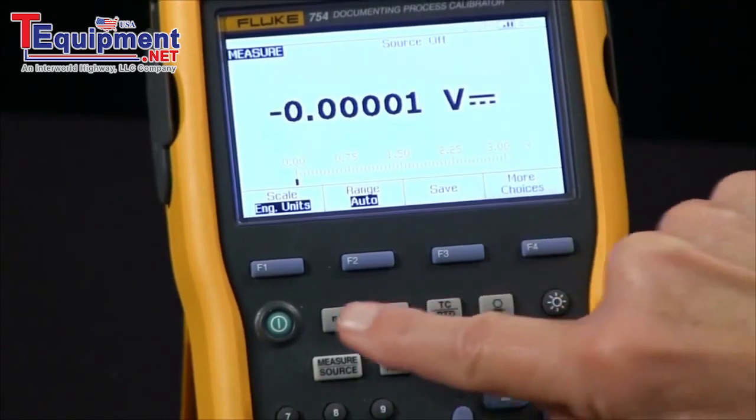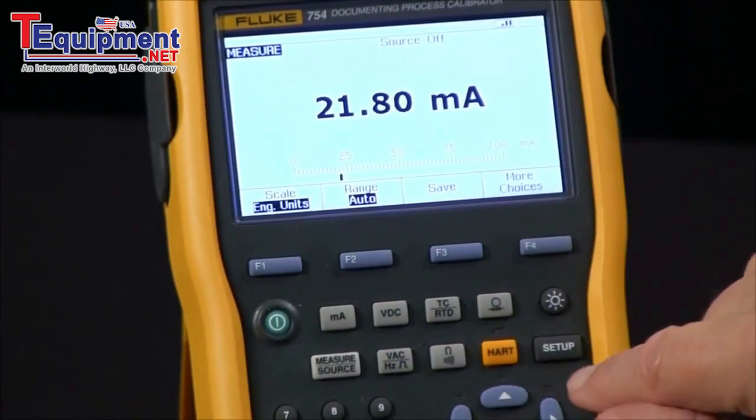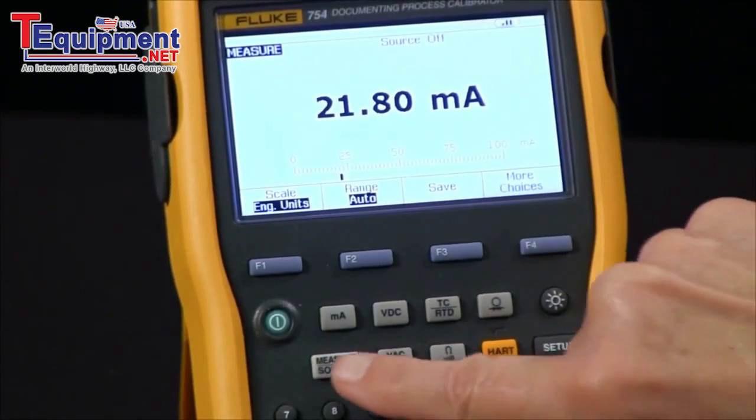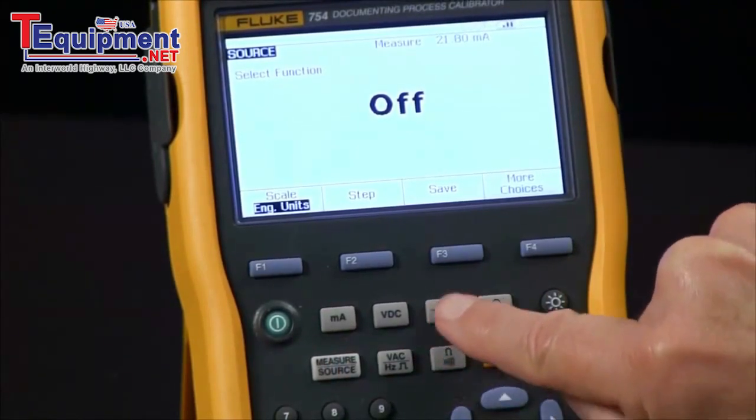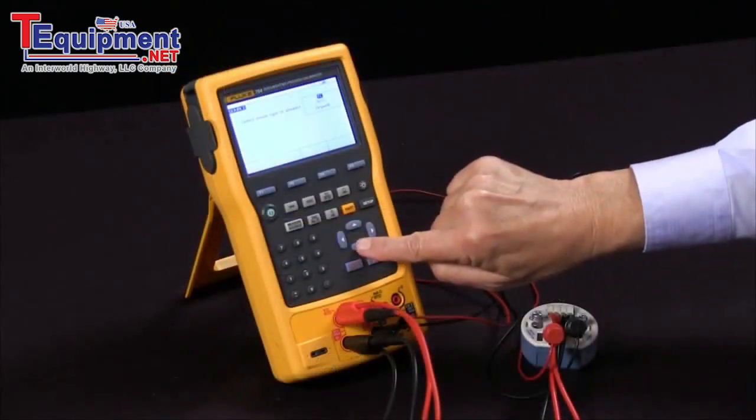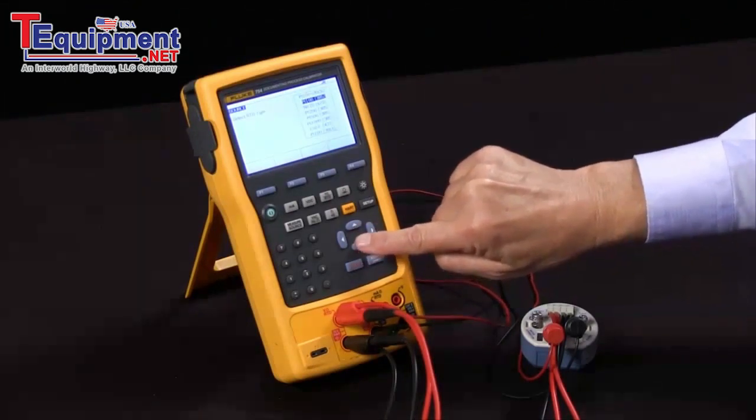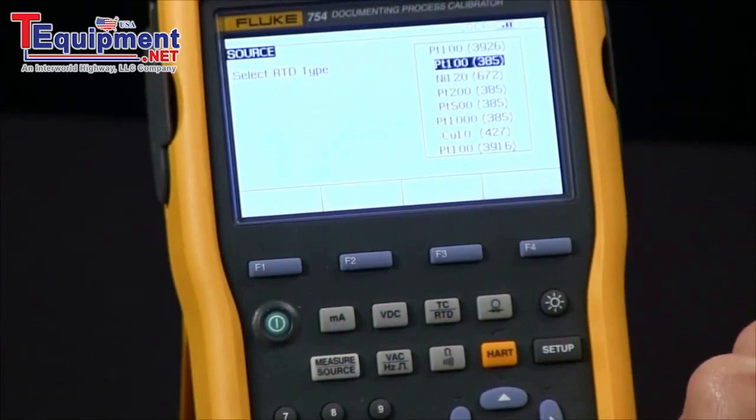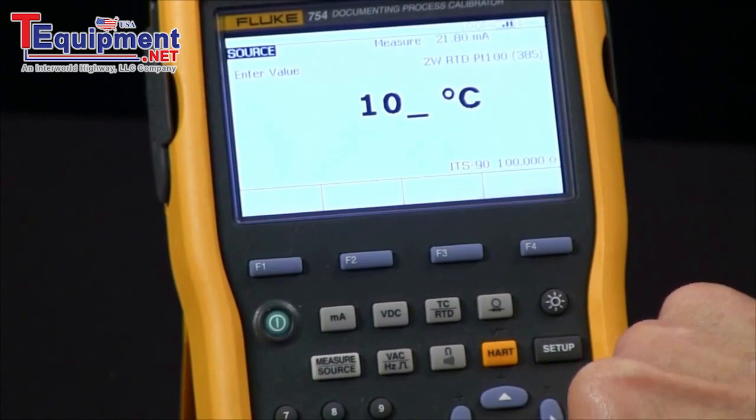If I go to milliamps measure, it's measuring 21.8 milliamps. If I go to source measure source and I select RTD, it asks me what type of RTD - platinum 100 ohm 385 - and it asks me to put in a temperature, so I'm going to put in 100 degrees.